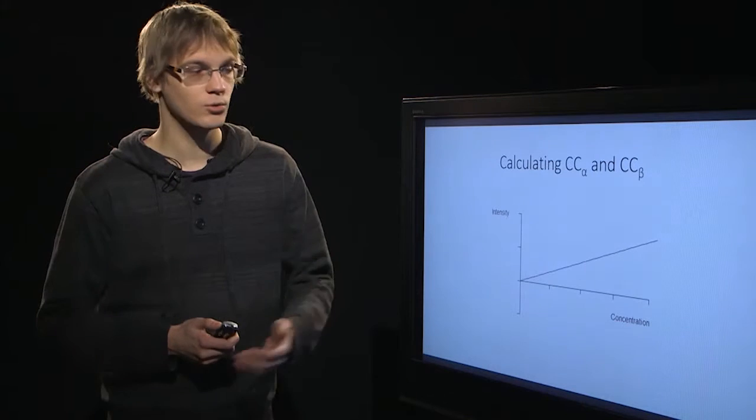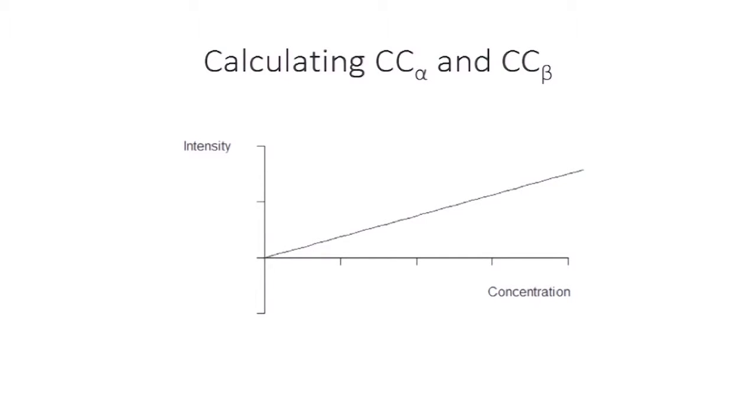Here we have a calibration function in the intensity and concentration scale, and let's say that we already know the distribution of intensity values at the blank sample. Now we can calculate this decision limit using the standard deviation and the mean of the blank samples. And using the calibration function, we can find the decision limit in the concentration scale.